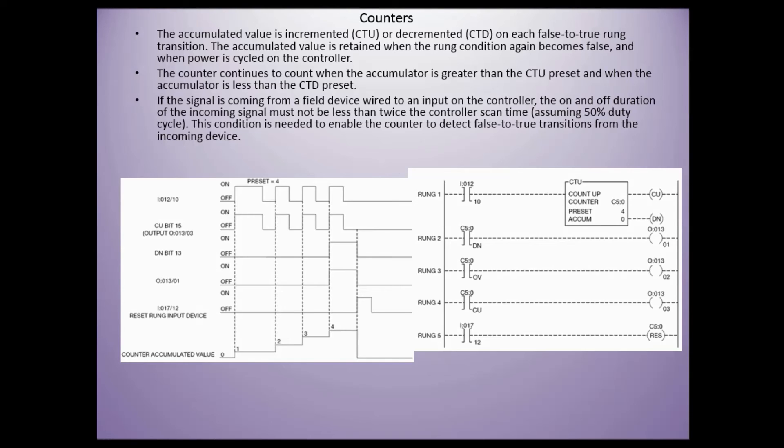The cumulative value is retained when the rung condition becomes false and when the power is cycled on the controller. That accumulated value will be retained in that counter. The counter continues to count when the accumulated is greater than the preset and when the accumulator is less than the preset in the CTD.